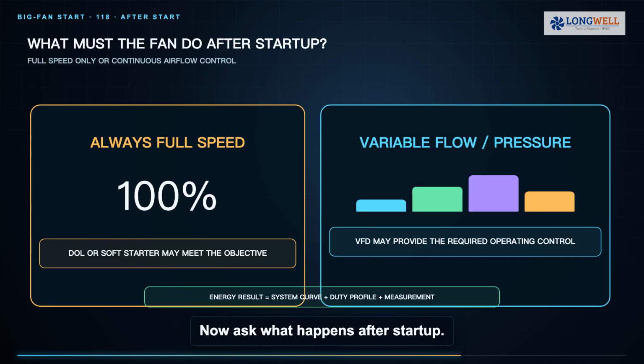Now ask what happens after startup. If the fan always runs at full speed and the network can accept the start, DOL or a soft starter may meet the objective with less control complexity. If the process must vary airflow or pressure, a VFD may deliver the required operating control and possible part load energy reduction. Savings depend on the system curve, duty profile, and measured input power.